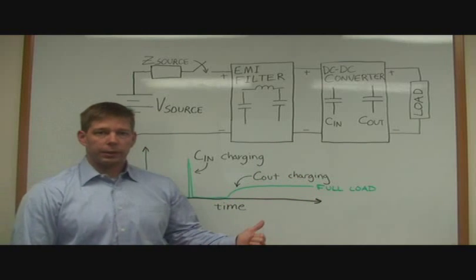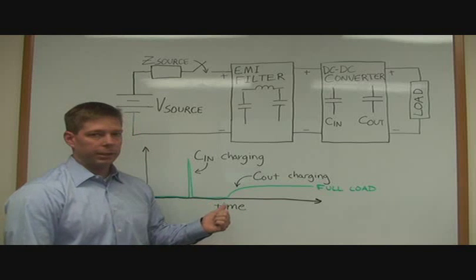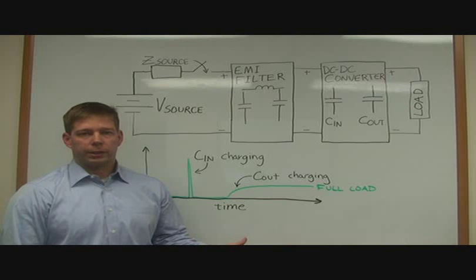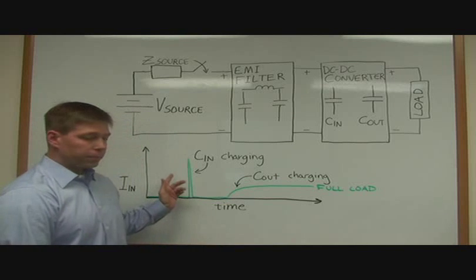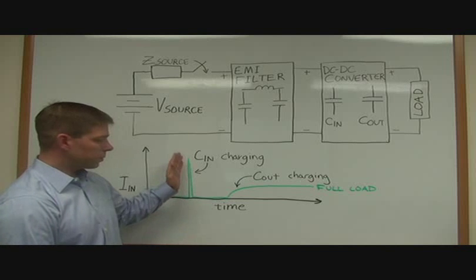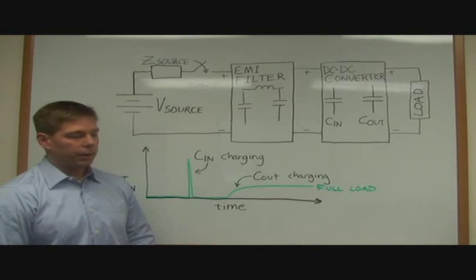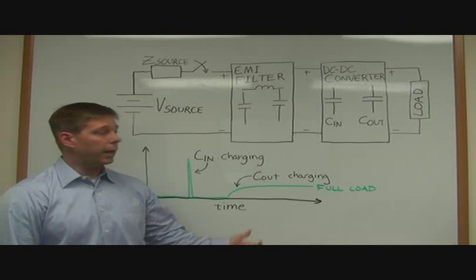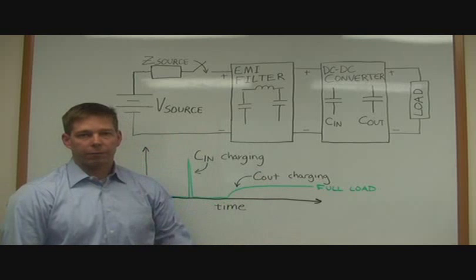The inrush current that occurs on the startup of a DC-to-DC converter system like this is composed of two regions. The graph here shows there's an initial spike in current that's caused by the charging of the input capacitance in the DC-to-DC converter and any capacitance in the EMI filter.